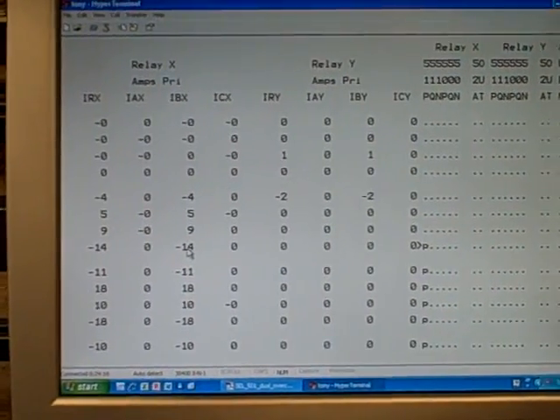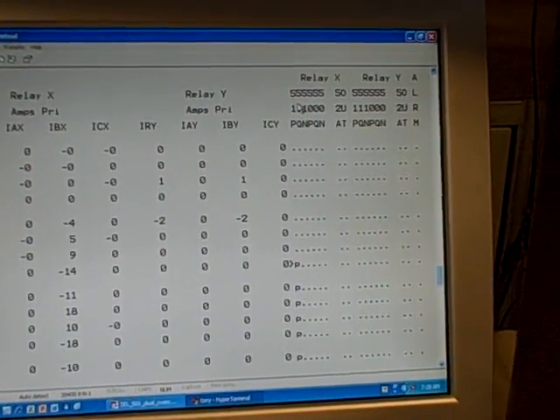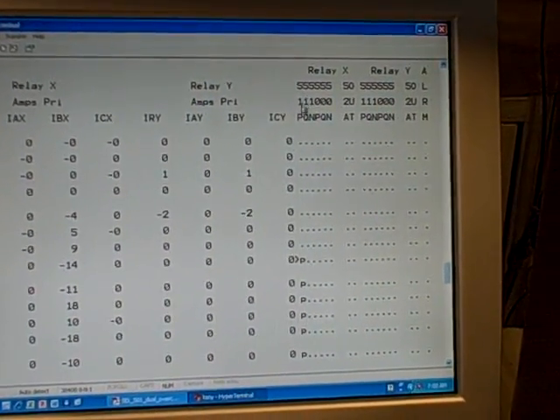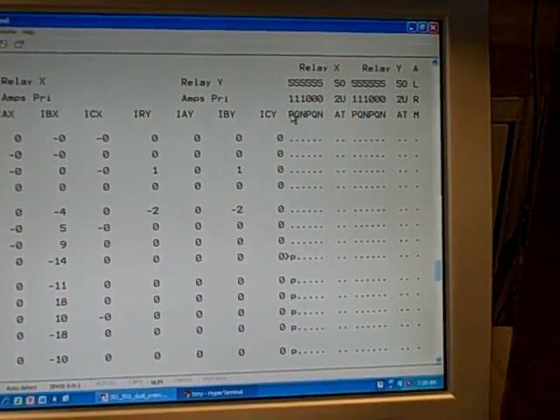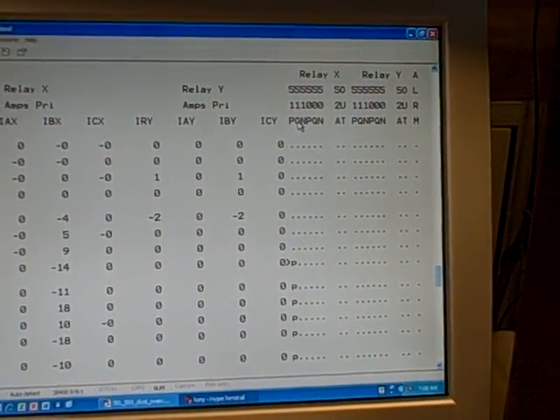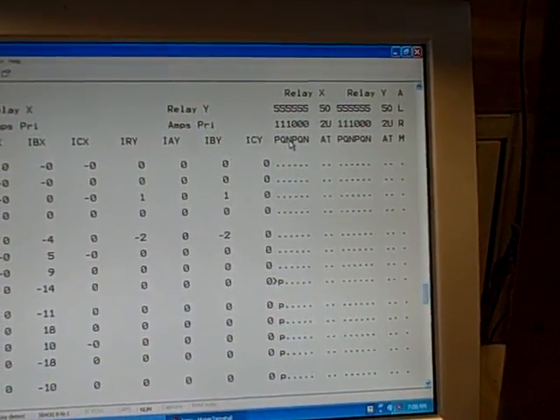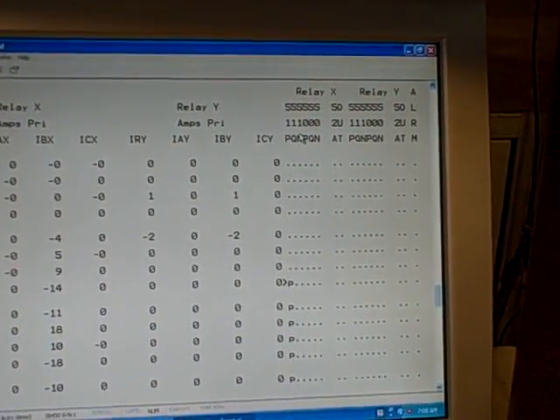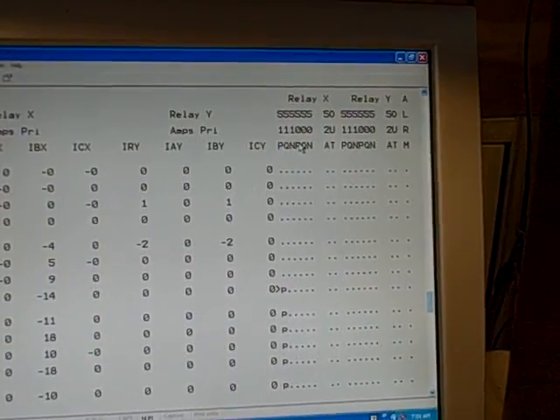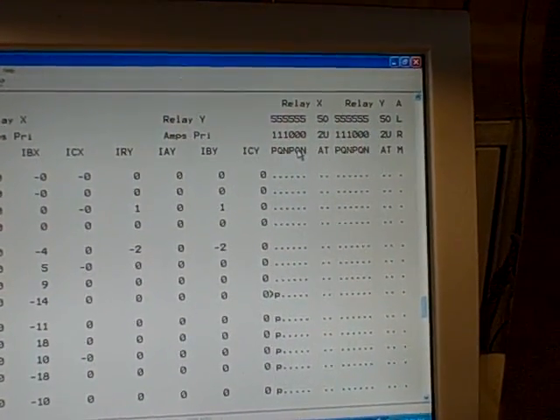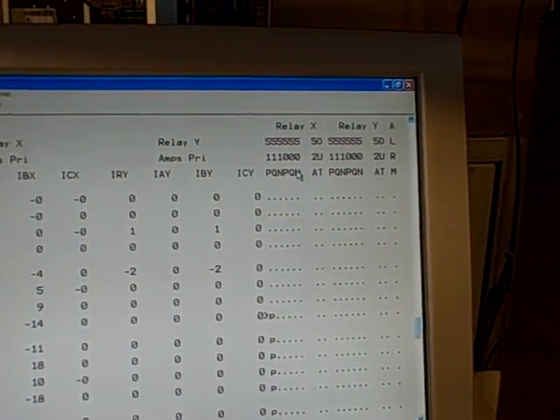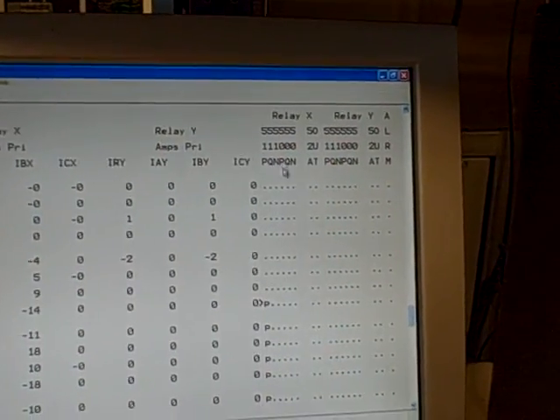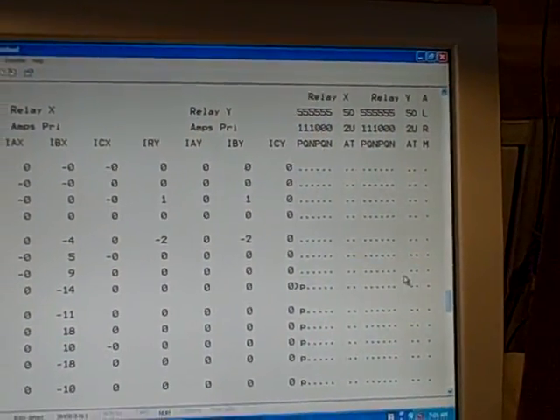Now over here on the right hand side of the display, we see indications of the elements inside the relay, whether or not they will actually pick up or initiate a trip. We have 51P, which is the phase time over current; 51Q, which is the negative sequence time over current; 51N, which is the neutral time over current or zero sequence. Then we have 50P, the instantaneous phase over current; 50Q, instantaneous negative sequence; and 50N, the instantaneous neutral or zero sequence. These dots here mean nothing's going on, nothing's picked up, nothing's tripped.